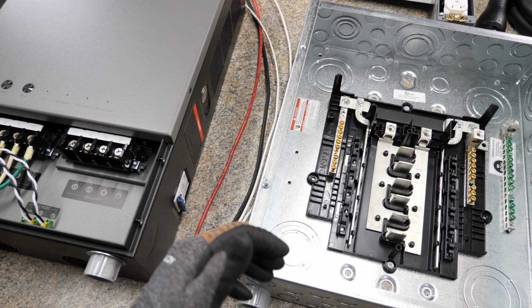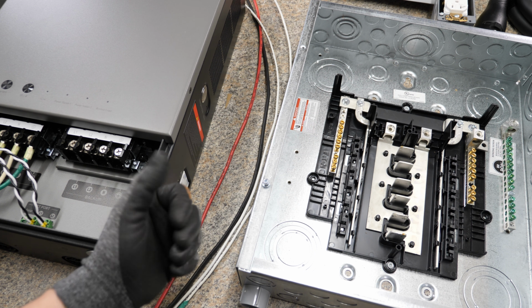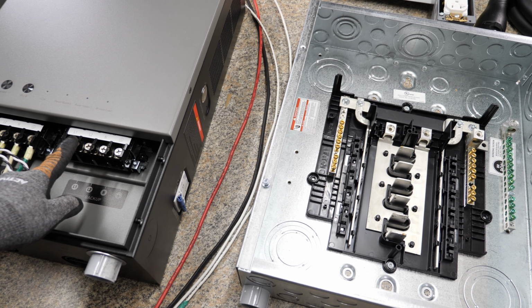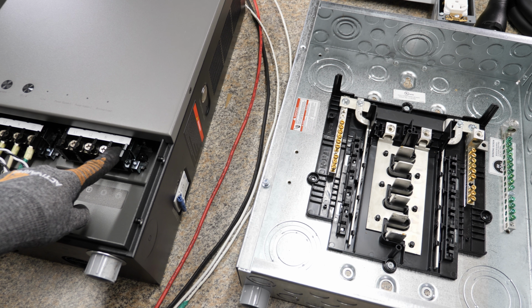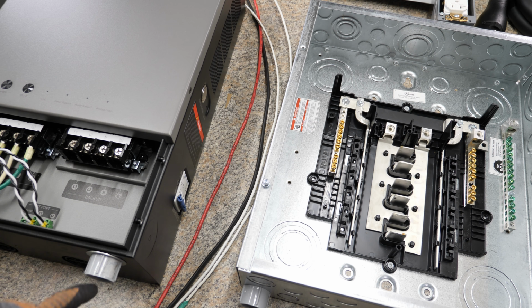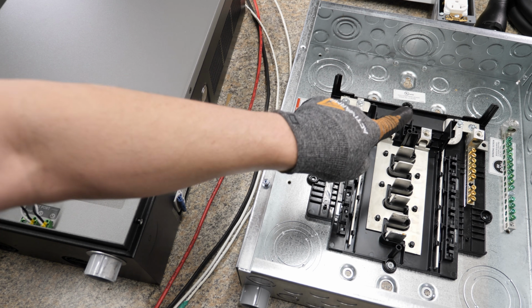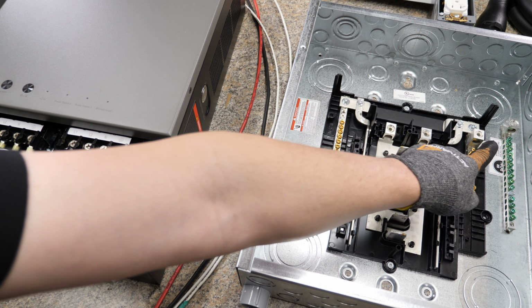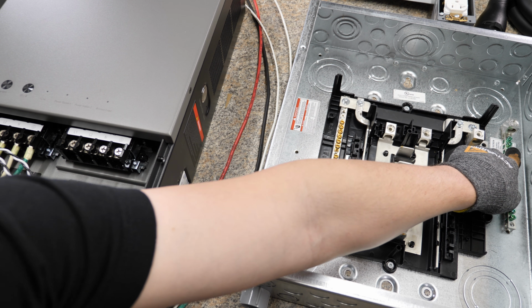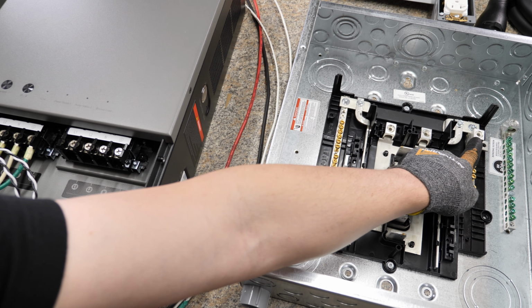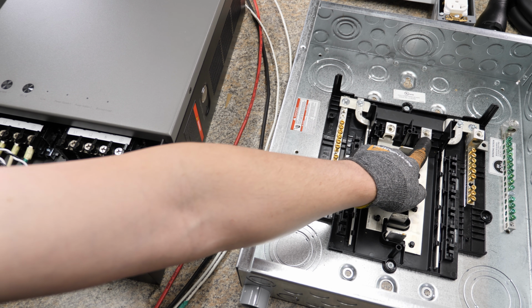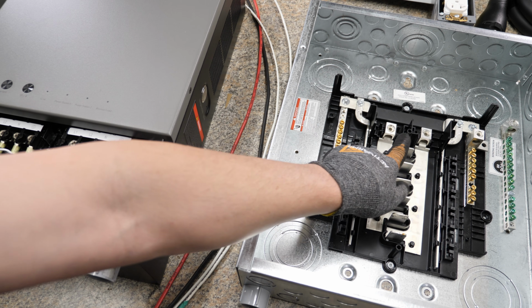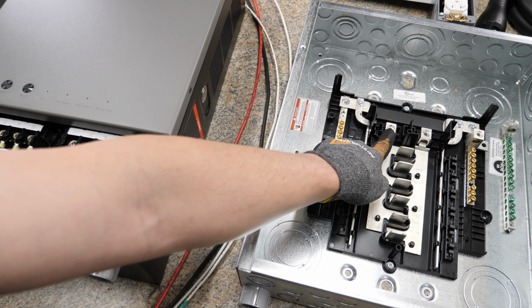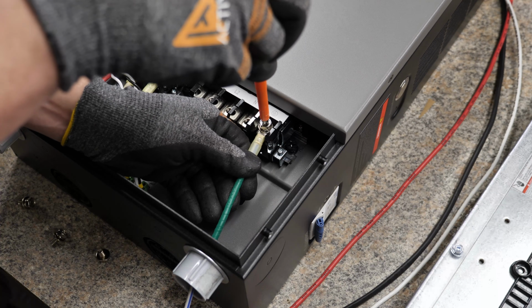It's going to be basically the same as we wired from the main panel to the home power panel. We have our L1, L2, neutral, and ground. Those wires connect here, going through this piece of conduit, then into the bottom side of the panel. They go up and loop around to the top side. Our ground goes right here, which we just installed. Our neutral goes to this lug right here. L2, which is red, goes to this lug, and L1, which is black, goes to this lug right here.